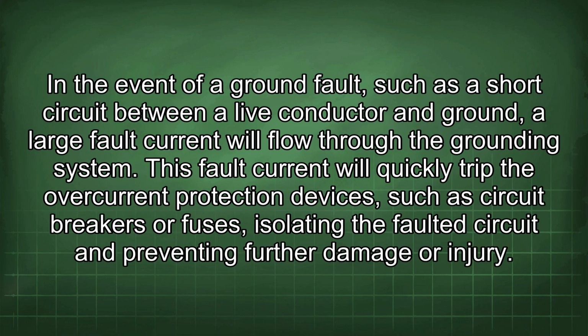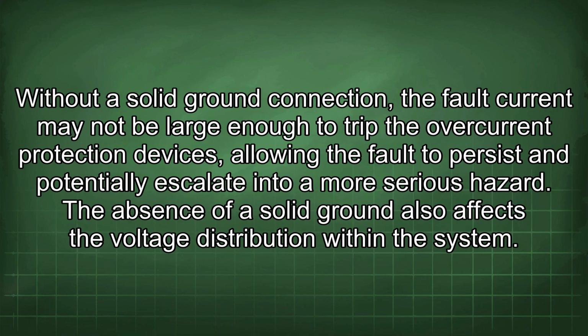In the event of a ground fault, such as a short circuit between a live conductor and ground, a large fault current will flow through the grounding system. This fault current will quickly trip the overcurrent protection devices, such as circuit breakers or fuses, isolating the faulted circuit and preventing further damage or injury. Without a solid ground connection, the fault current may not be large enough to trip the overcurrent protection devices, allowing the fault to persist and potentially escalate into a more serious hazard.